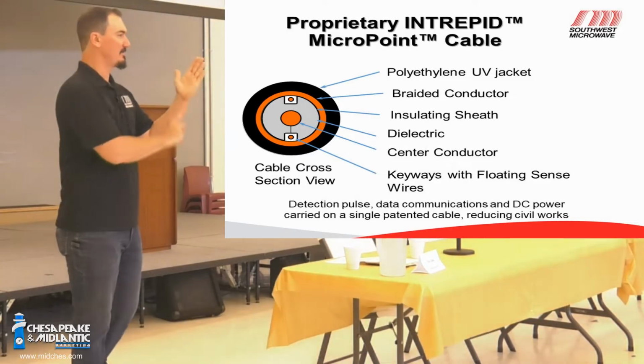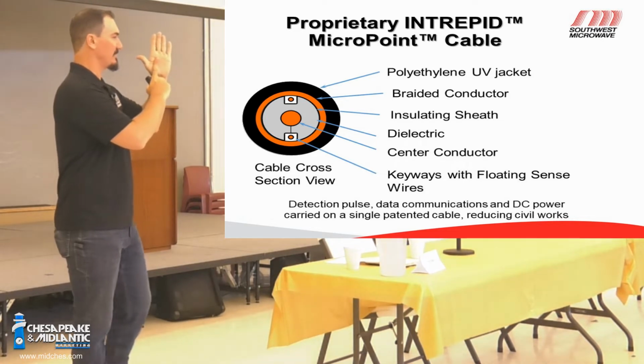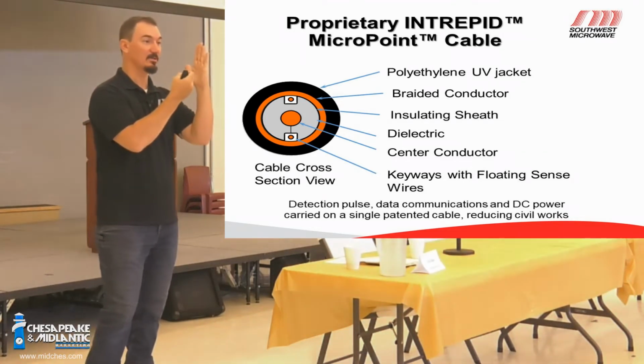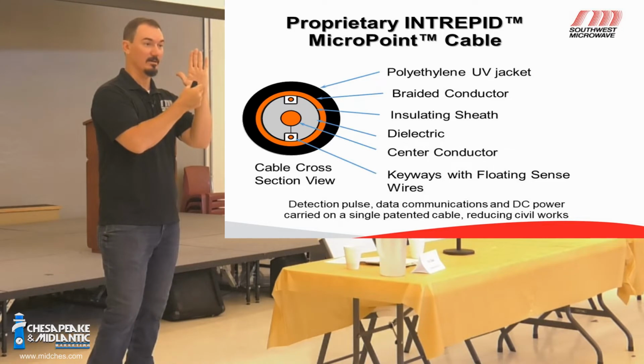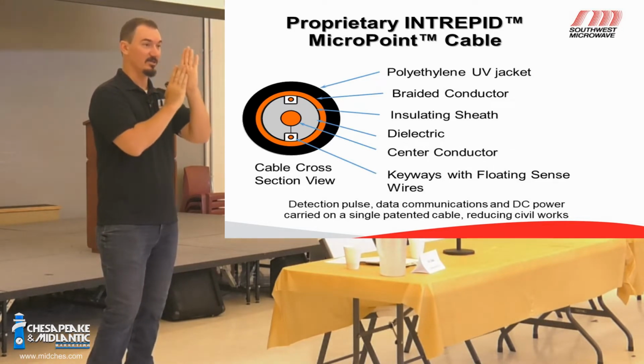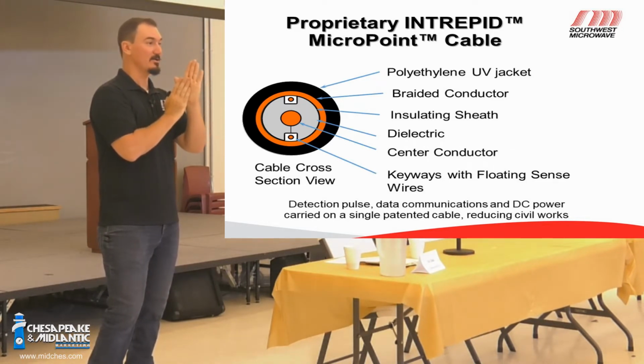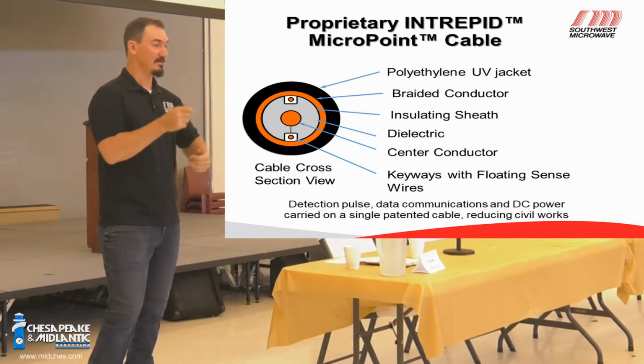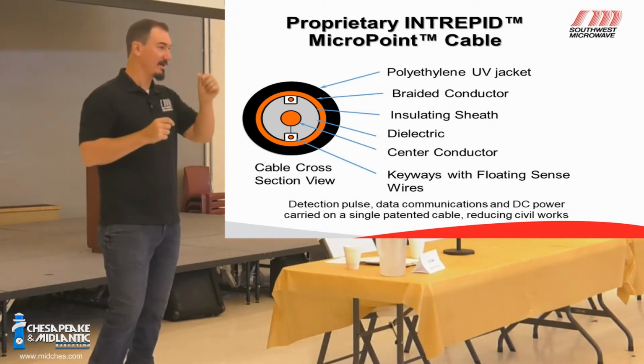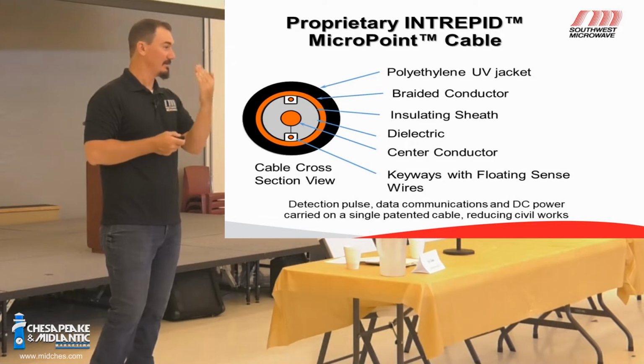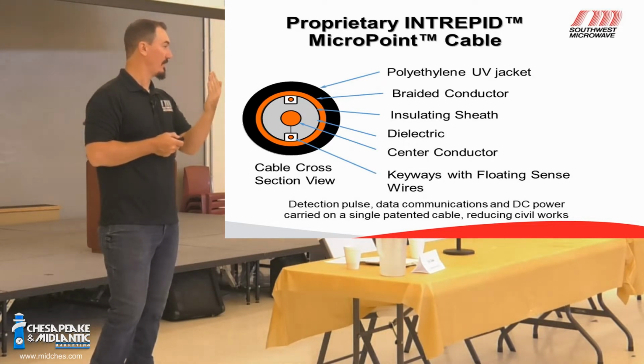So these little sensor wires move around inside there. The tinfoil shielding provides EMI RFI protection. The braid provides ground. When you open each of your processors, you'll notice that the sensor cable comes up and is attached flush onto that board. Well, if you move that cable and look, there's actually a braid on the board. And those braids should be flush against each other. If you're checking on your installer and you open one of those processors and you pull that little block off and that braid isn't flush up against the other one, then the installer landed that cable the wrong way.